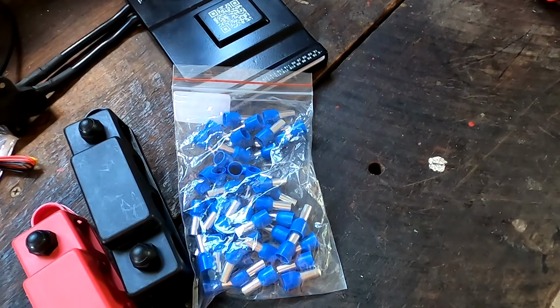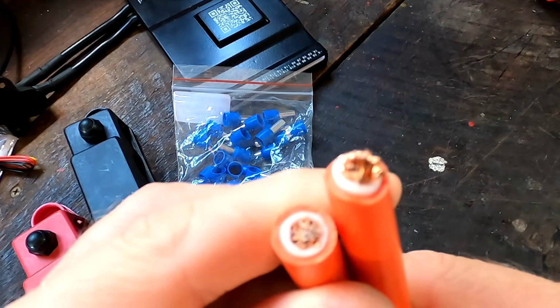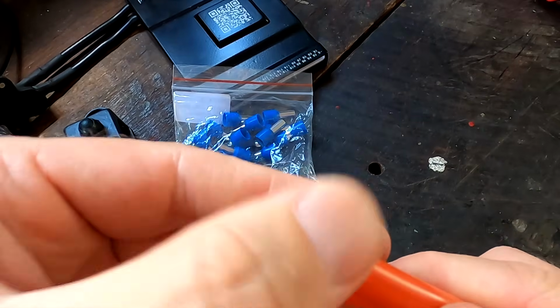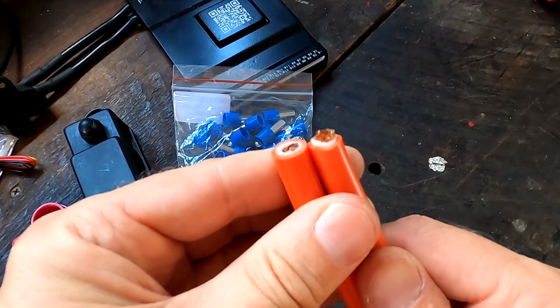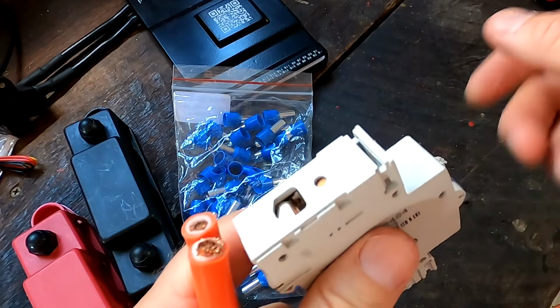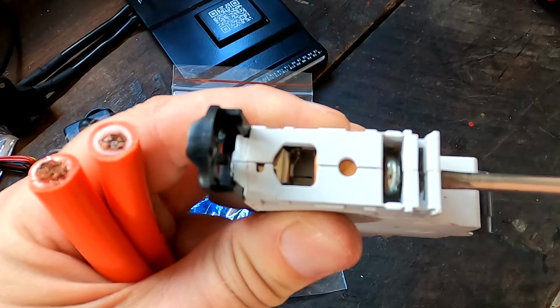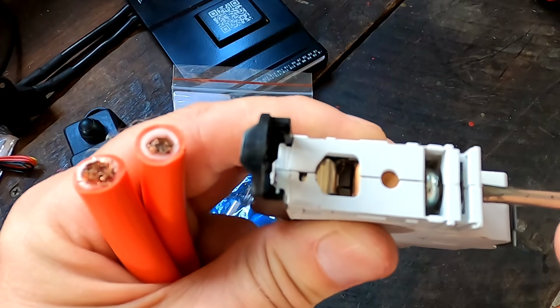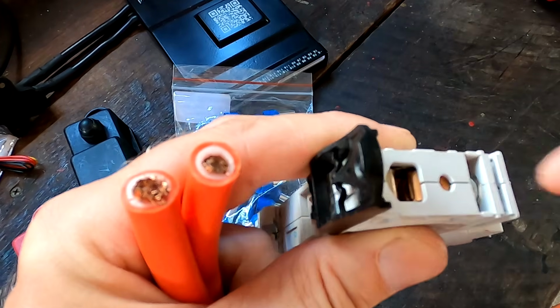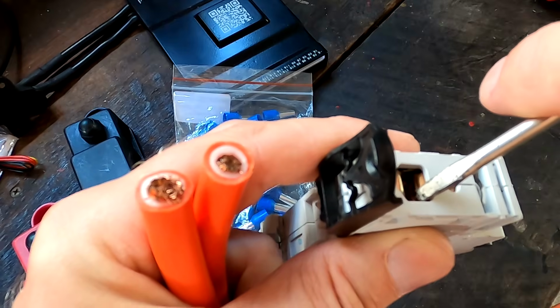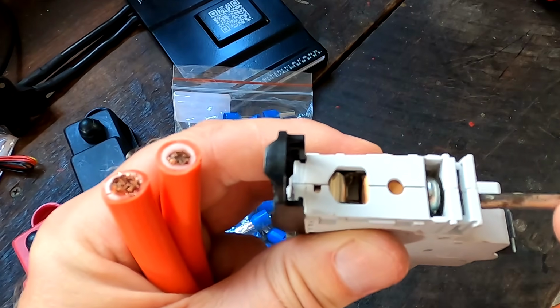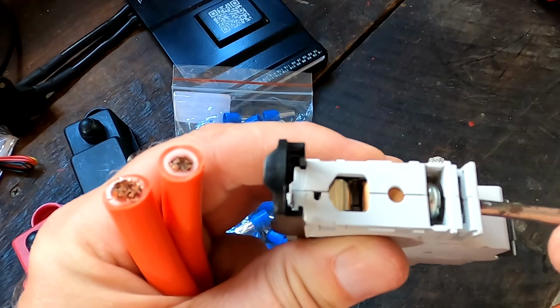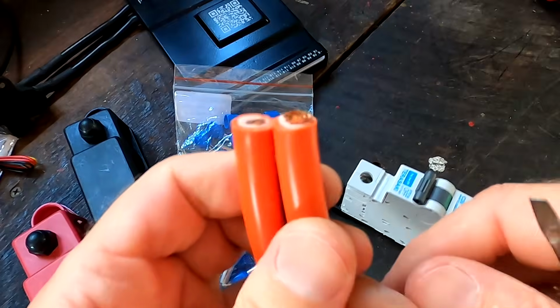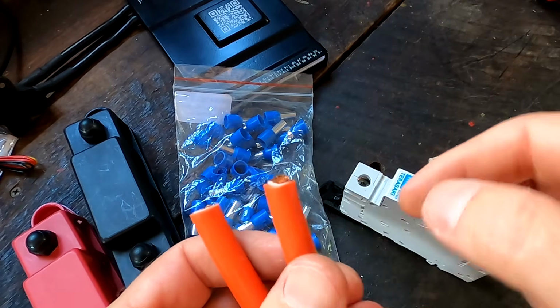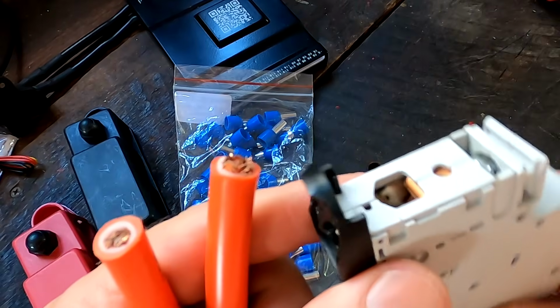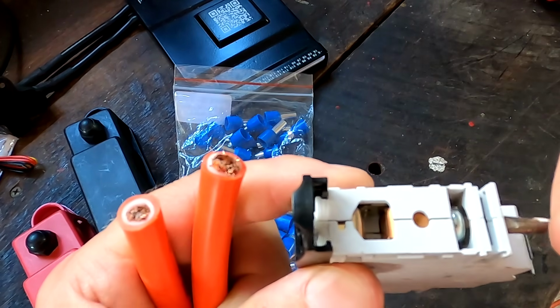Here comes the big question. To ferrule or not to ferrule? These multi-stranded cables here have really fine cores. And I guess it always comes down to where you want to screw them in. If you have a circuit breaker or something, they usually have a chamber. See, it's like a clamp which is coming up, and this provides a very good grip to the cable and to the actual contact here at the top. See the copper part there? This is the actual contact, and this mechanic only clamps the cable against the contact. So you can use a bare cable here, strip off the insulation, and feed this into the terminal directly. You don't need a ferrule for these clamp contacts.